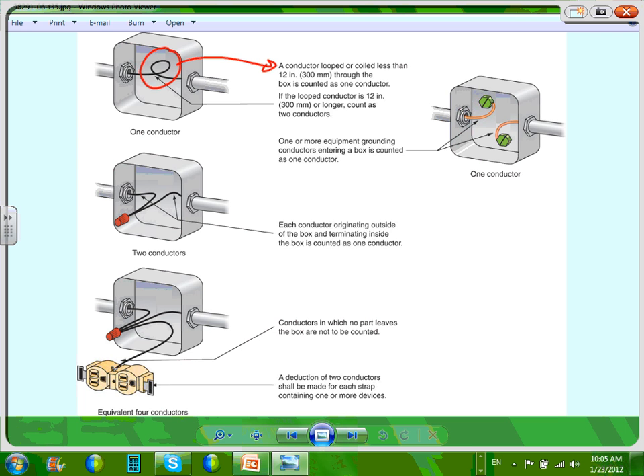If you have a loop like this, and the conductor is looped or coiled less than 12 inches through the box, it counts as 1. So remember that loop we talked about? What I like about these are the pictures that come with them, guys. If you loop it 12 inches or more, it counts as 2. If you loop it less than 12, it counts as 1. If the conductor is going right through, it counts as 1. If the conductor is spliced, it counts as 2.